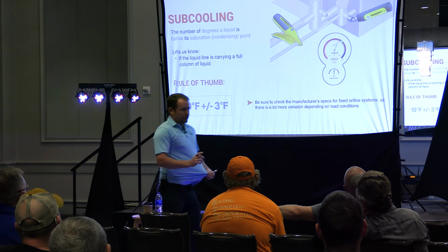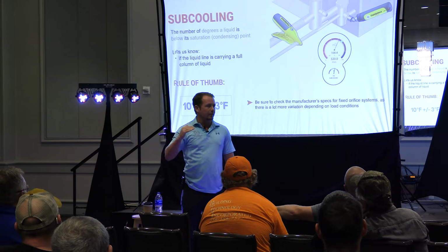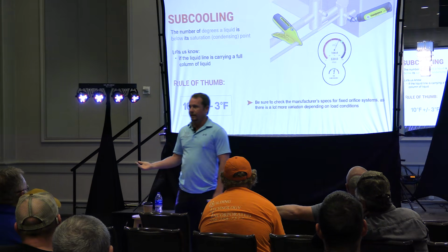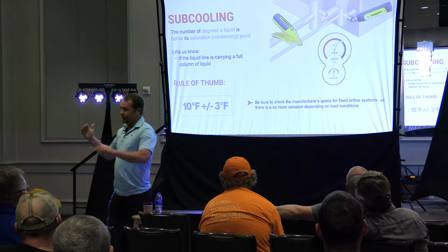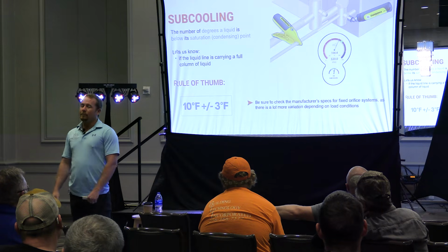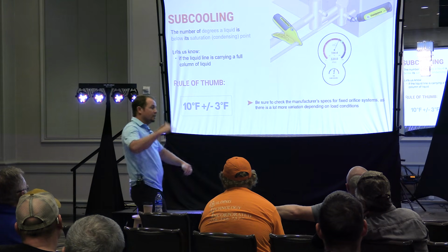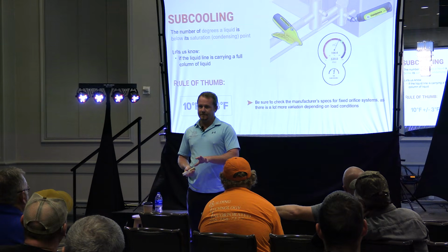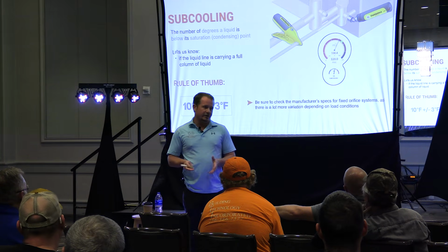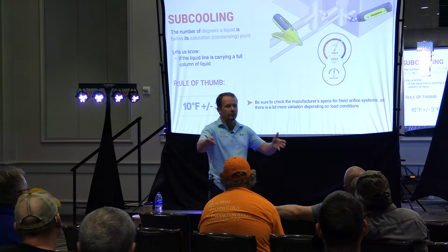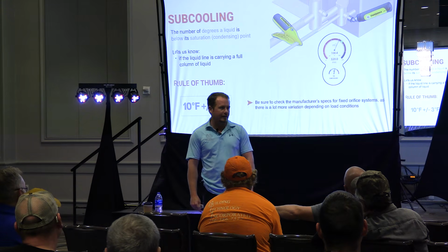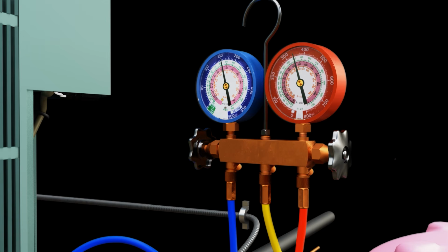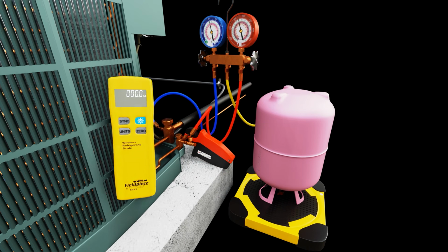So what is the purpose of subcool? When we measure it, it tells us that, right? But why do we care? Because we want to know, are we feeding our metering device with a full column of liquid? Full stop. A lot of people will say, more subcool equals more efficiency. It's a tricky thing. Because when you increase the charge in your system, so you take a typical system that you guys work on every day, whatever you sell, right? And it's like, all right, my subcool's low. I'm gonna get my subcool up. And you add refrigerant to the system.